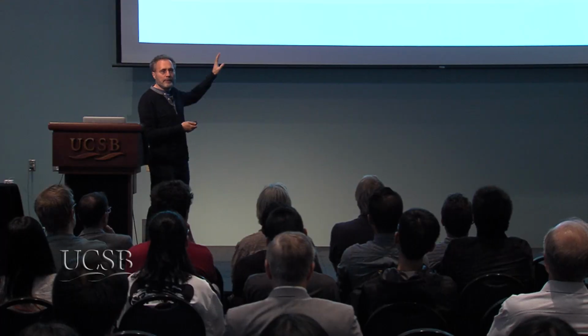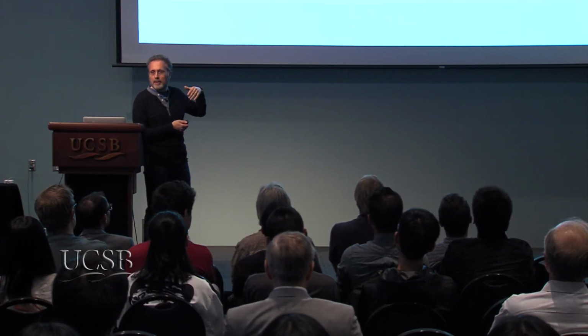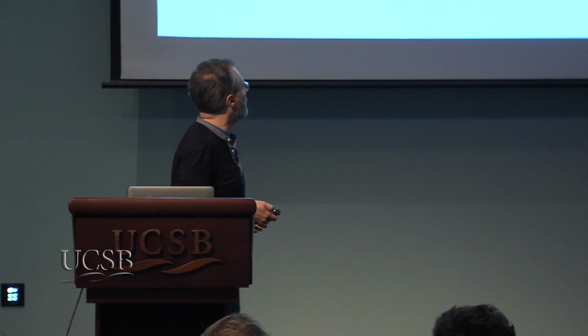Here's another way of looking at it. The study split data centers by type, and interestingly, the very large and very small ones do better than the middle. For small server closets, people don't worry much about cooling - air just dissipates naturally, so they skip air conditioning and save a little. The typical server room has a factor of 2 to 2.5 overhead, which is pretty bad. But the hyperscale value was 1.2, just 20% overhead - much better than 80% or 200% overhead.